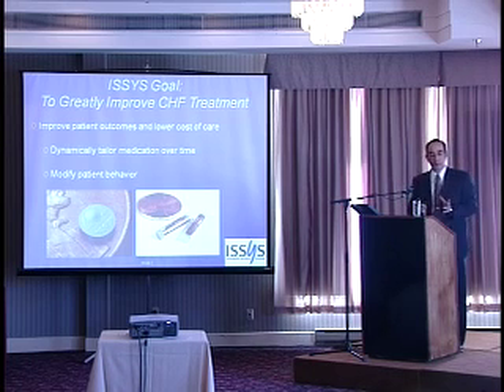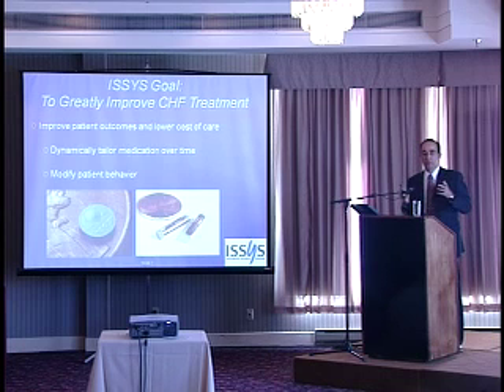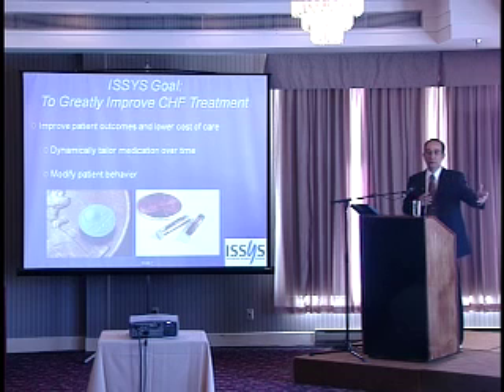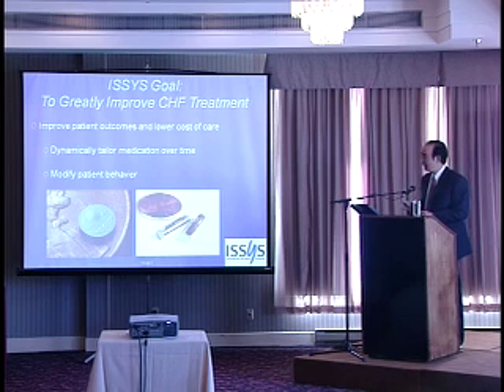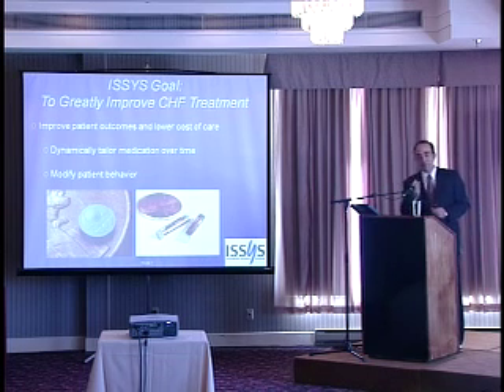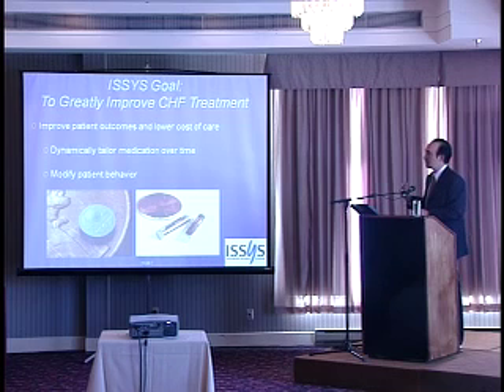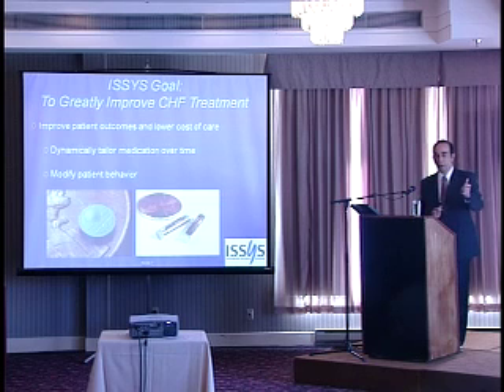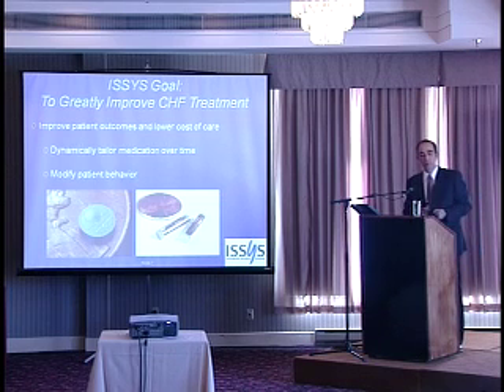The reason is, when I look at our device, which back then was just what we call a dumb sensing element, a capacitive pressure sensor and a coil, it would not go where we wanted to go, and we would not cover all the applications that we wanted to cover. So by having a circular device, we are able to put that in front side of this glass tube, and now we have a cylindrical device. This pressure sensor is hermetically sealed from the environment, and again, you can hermetically seal this from the rest of the system, so any outgassing in the system from your coil or from any other element will not cause a drift in your pressure sensor. When you're looking to put a pressure sensor within the body that you hope lasts more than 10 years, stability is extremely important.